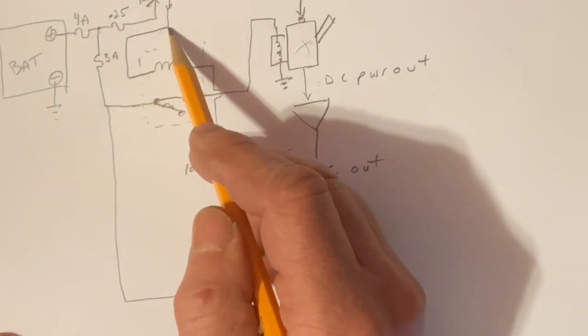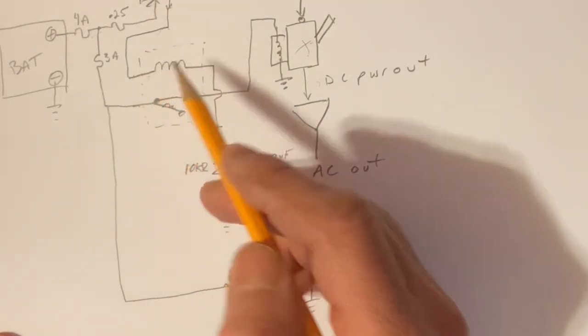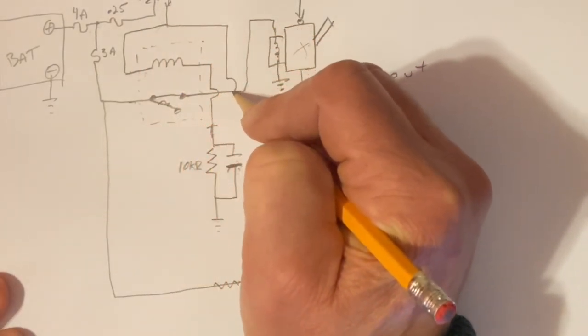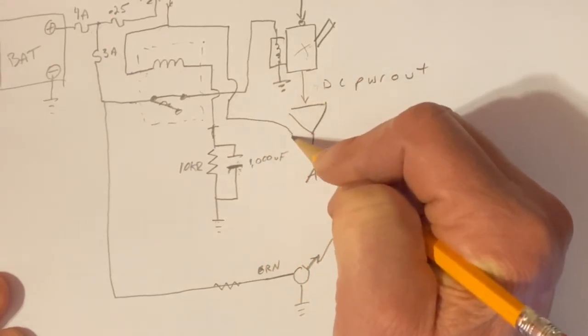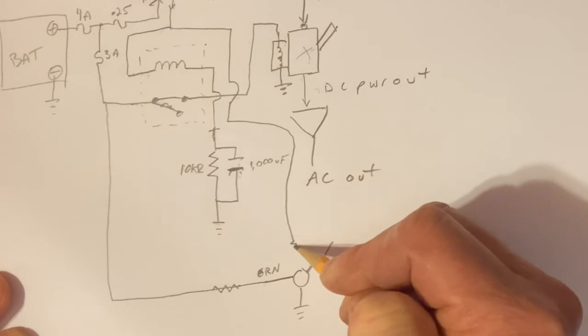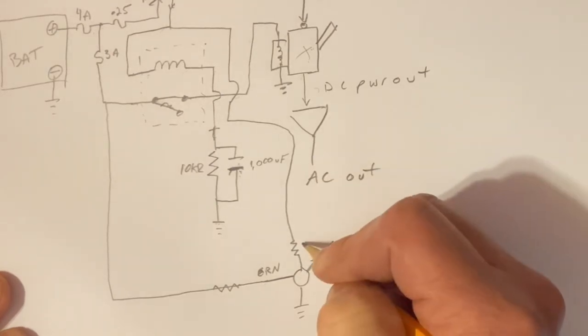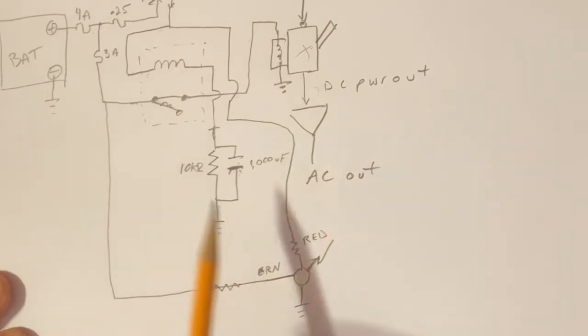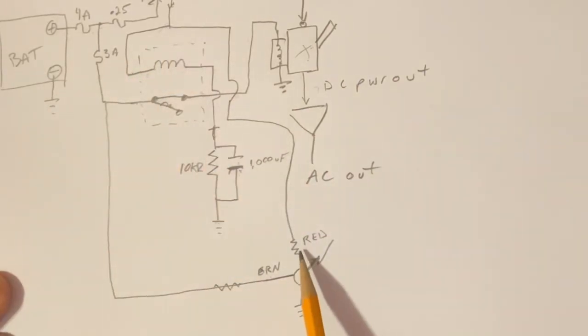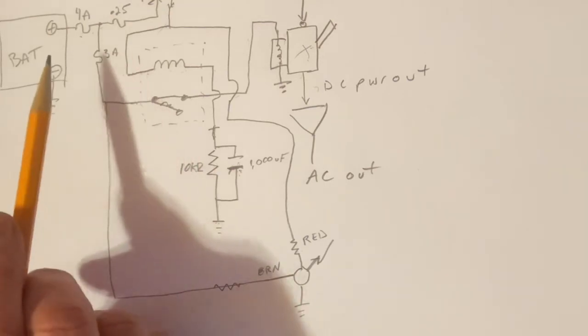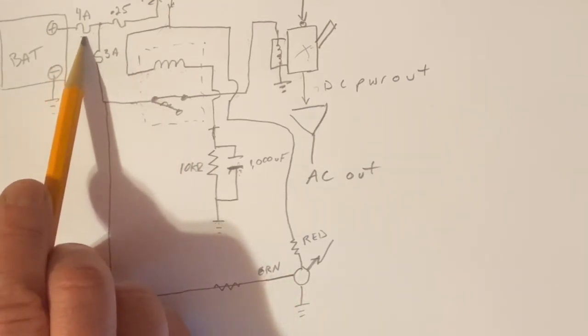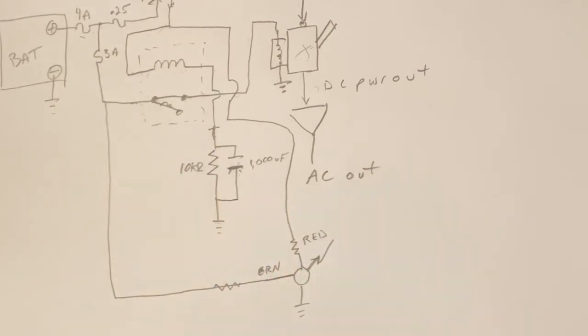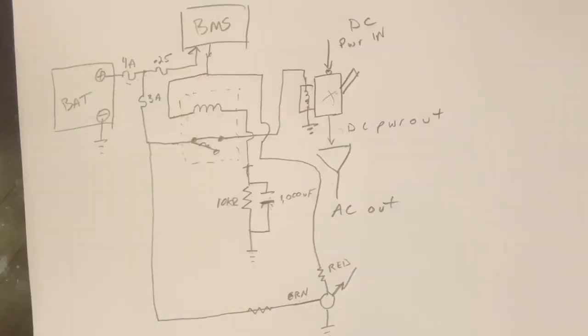When the BMS sends a signal to the coil that tells us something is not right, that same signal goes, you'll have to forgive my drawing, I am not an artist, again through a dropping resistor, and this goes to the red side. So when this goes high, the red overrides the green color and it glows bright red. One of the LEDs in the circuit is wired to glow red if this fuse blows. So that way we have an indication that the entire BMS has gone down, and we'll need to troubleshoot why that is. So this is a basic overall schematic of how that control system works.